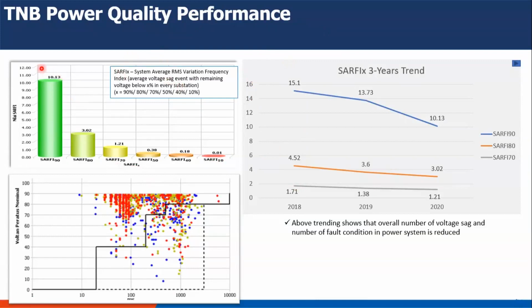We can see that SARFI 90 is about 10.13, meaning an average of 10.13 voltage sags happen in one year. SARFI 80 is 3.02. SARFI 70 is 1.21, meaning on average only one voltage sag happens below 70 per year, and so on. So SARFI X means 90, 80, 70, 50, 40, and 10.